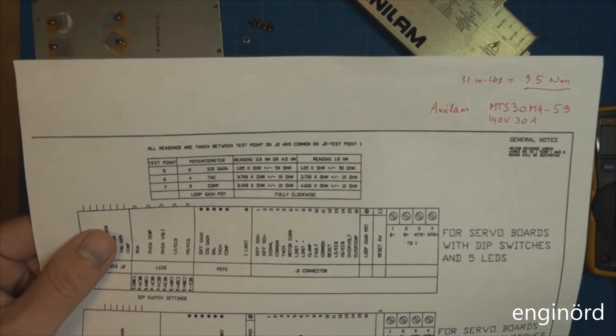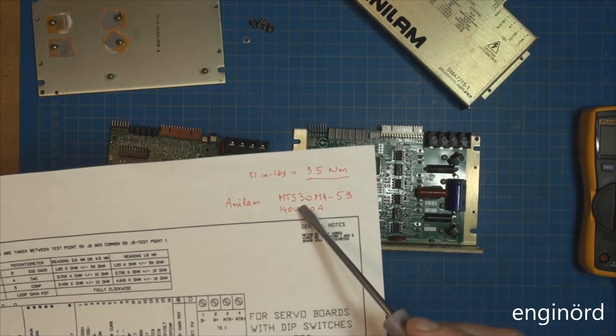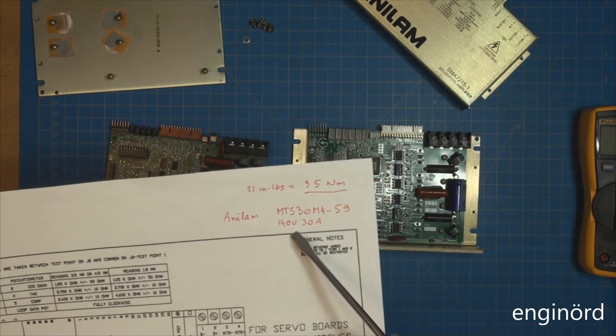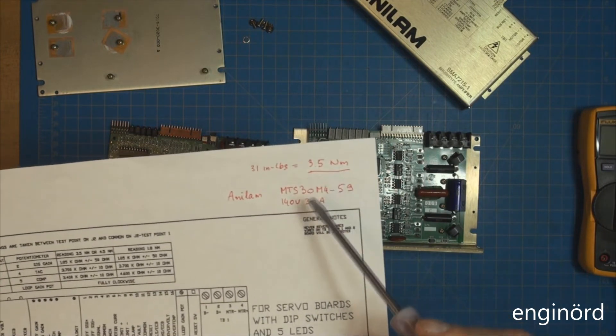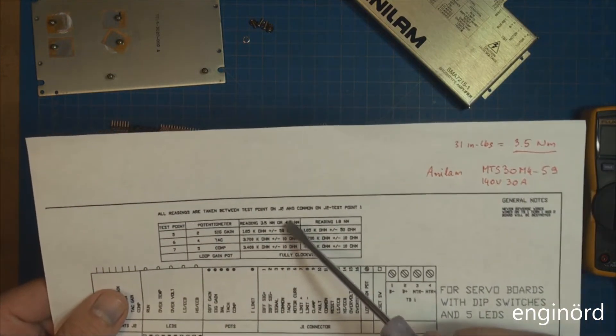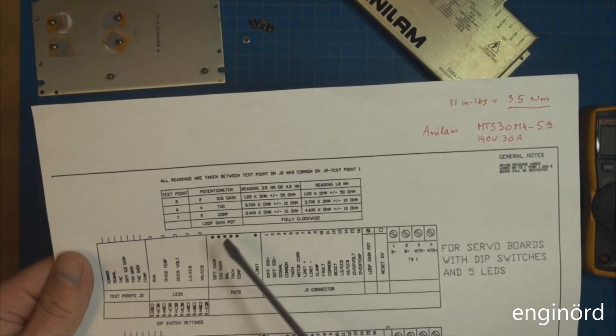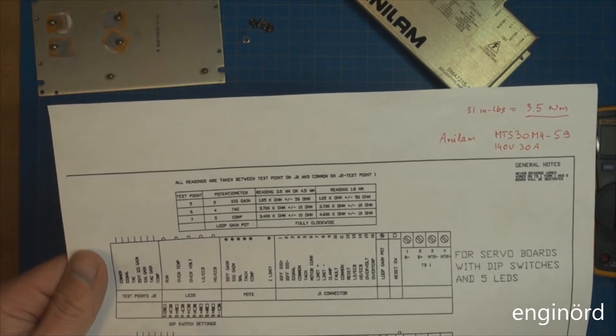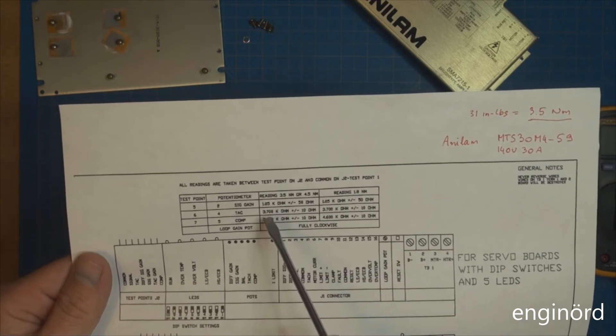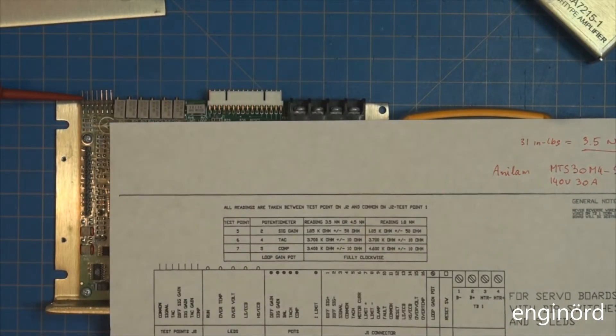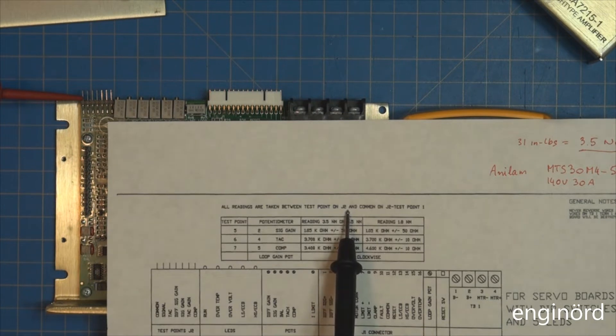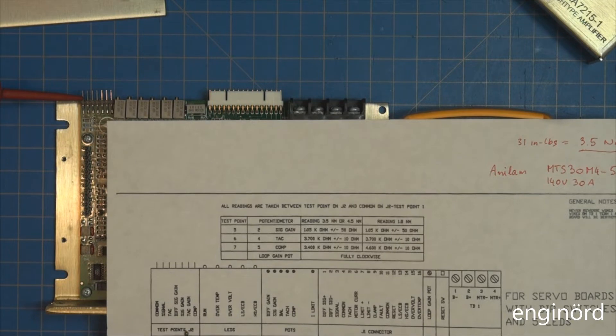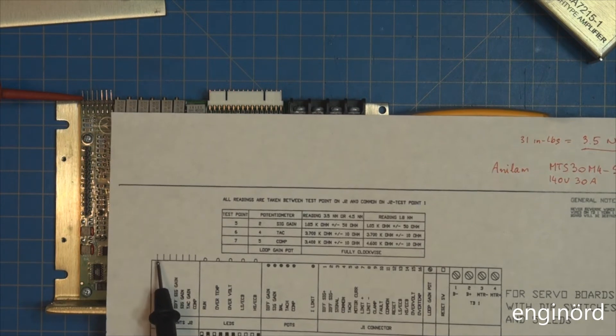The motors in my machine are MTS30M4-59, 140 volt 30 amp. According to the nameplate they are 31 inch pounds which equals to 3.5 newton meters, so I need to adhere to this column here. What I need to do when the servo amp is disconnected and not powered up is find the test points, measure the resistances here, and adjust the potentiometers accordingly. Here's test point J2 and the common on the left side - that is point 1. There's seven leads, and indeed there's seven test points in this area.